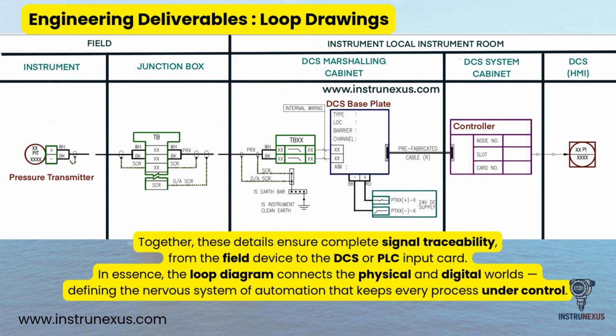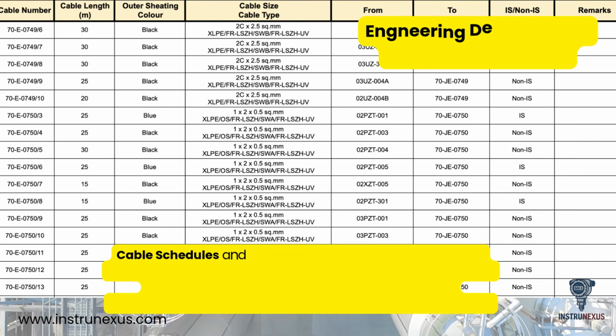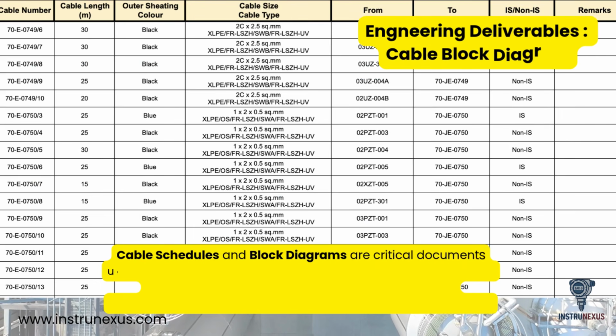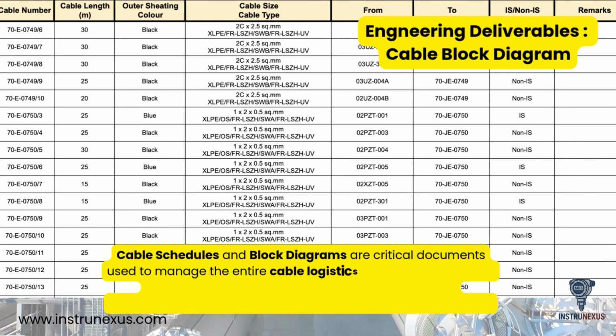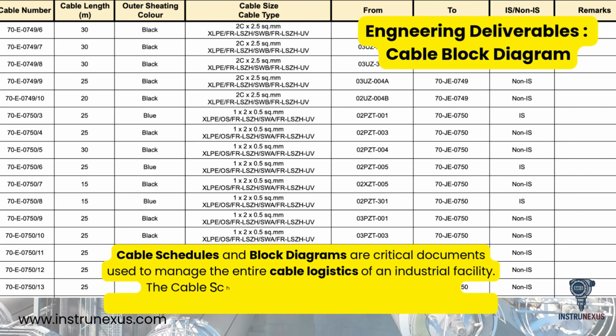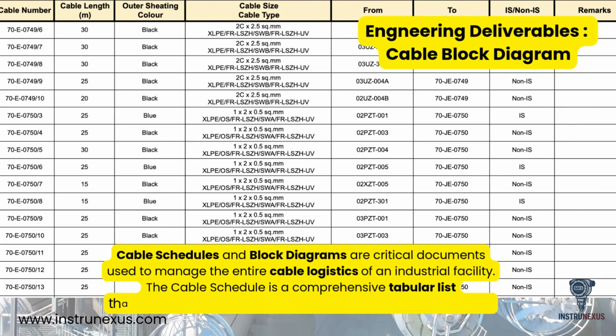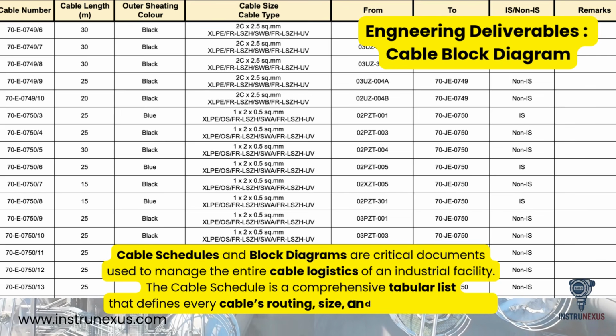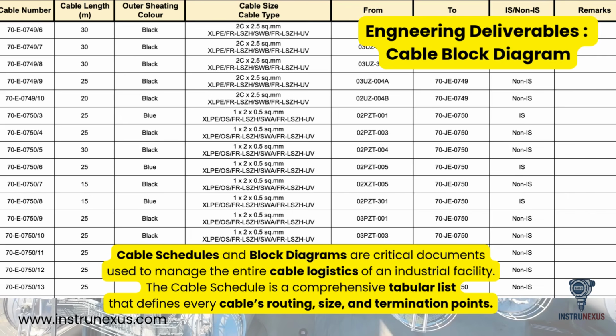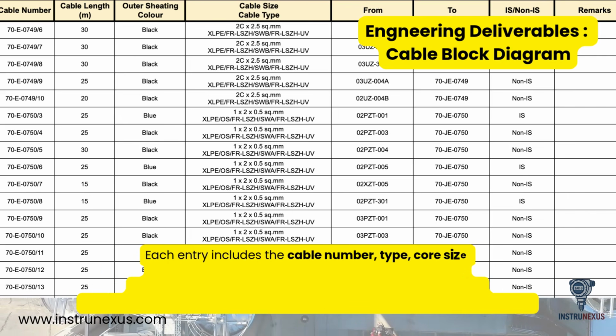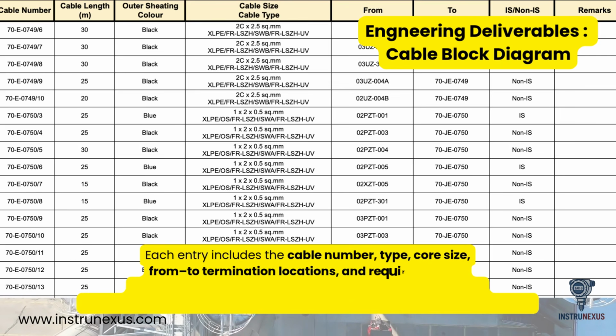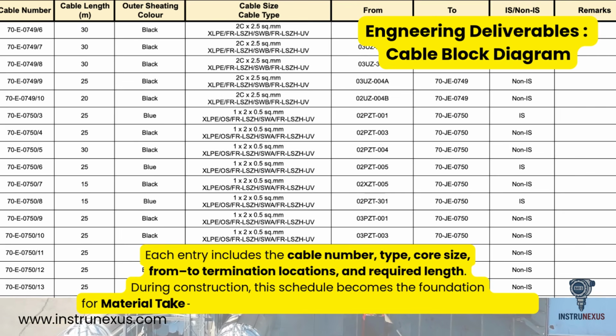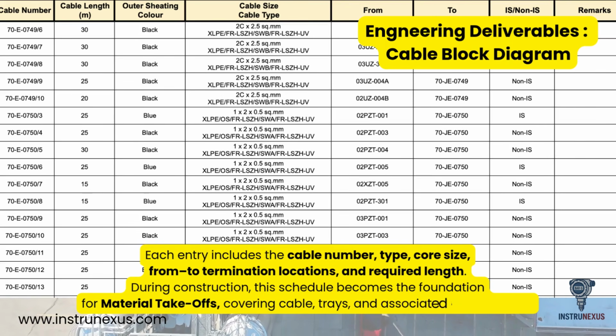Cable schedules and block diagrams are critical documents used to manage the entire cable logistics of an industrial facility. The cable schedule is a comprehensive tabular list that defines every cable's routing, size, and termination points. Each entry includes the cable number, type, core size, from-to termination locations, and required length. During construction, this schedule becomes the foundation for material takeoffs, covering cable, trays, and associated infrastructure.